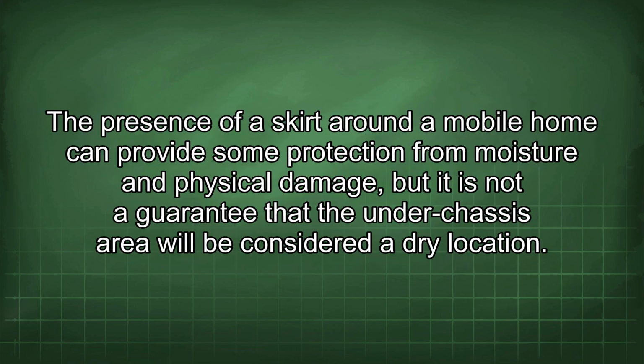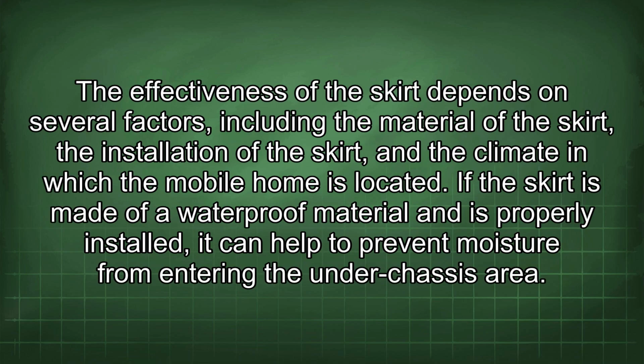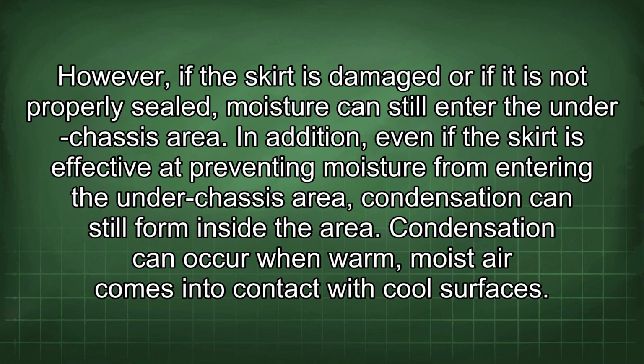The presence of a skirt around a mobile home can provide some protection from moisture and physical damage, but it is not a guarantee that the under-chassis area will be considered a dry location. The effectiveness of the skirt depends on several factors, including the material of the skirt, the installation of the skirt, and the climate in which the mobile home is located. If the skirt is made of a waterproof material and is properly installed, it can help to prevent moisture from entering the under-chassis area. However, if the skirt is damaged or if it is not properly sealed, moisture can still enter the under-chassis area.